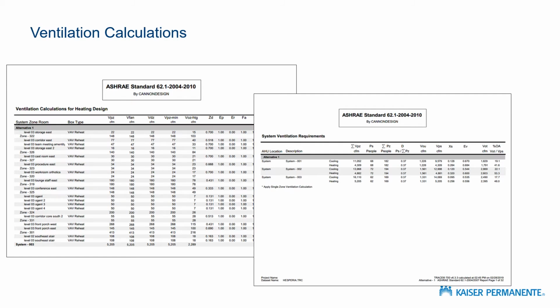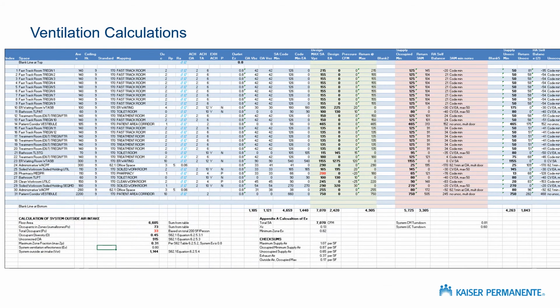For hospitals, those ventilation calculations are significantly more complicated. And we're actually starting to run our own set of ventilation calculations for every hospital project as a means of checking and doing peer review. The entire part 2 of this presentation is going to be about hospital air handler calculations. And the short version is, for Kaiser Hospital work, VAV calculations are a requirement. Variances to OSHPD are a requirement. Those aren't optional. And so there is quite a bit of calculations that need to be done. We'll talk about that in a little bit on this presentation.